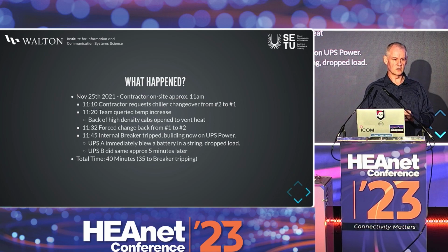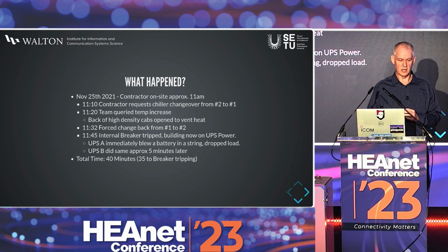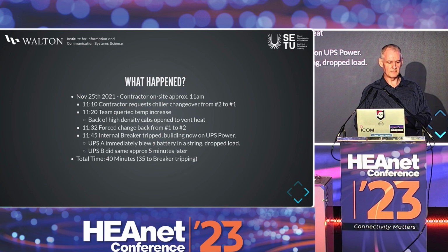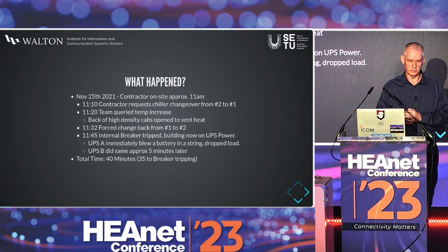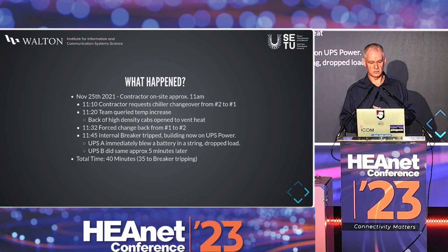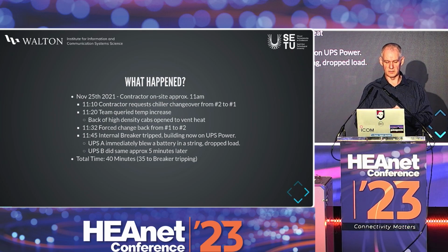By the time the alarm started going off, the guys were distracted with something else going on in the office. An internal breaker went in the building. At that point, a battery string failed on one UPS. About 5 minutes later, a second battery string blew, and that was it, game over. 35 minutes, start to finish - that's how long it took to happen.